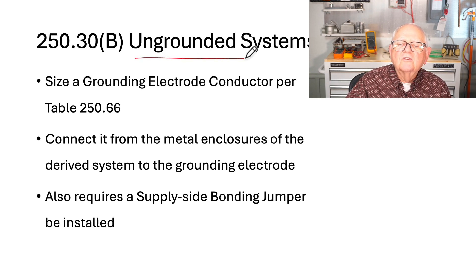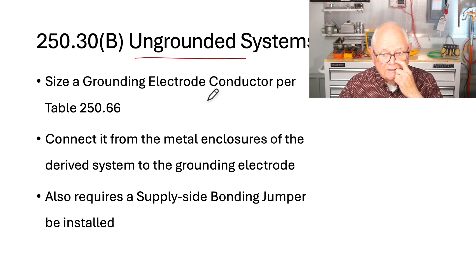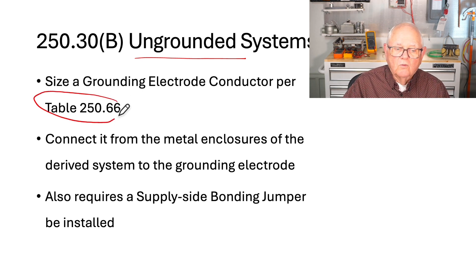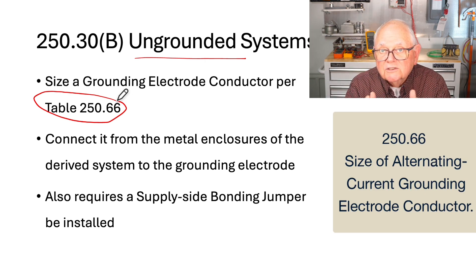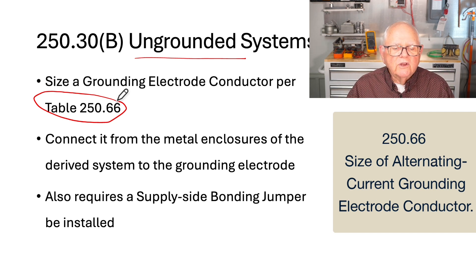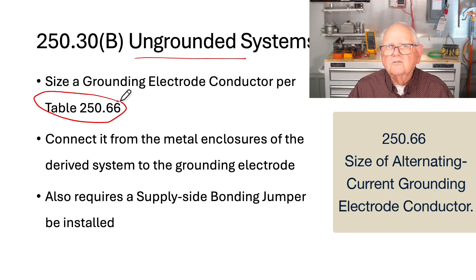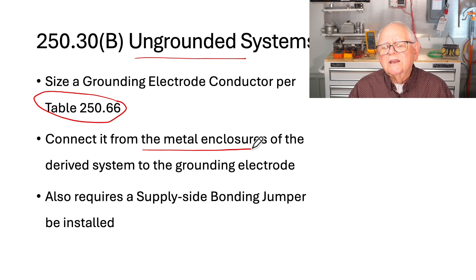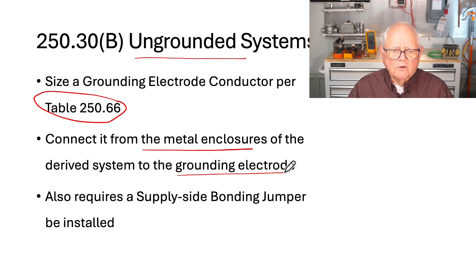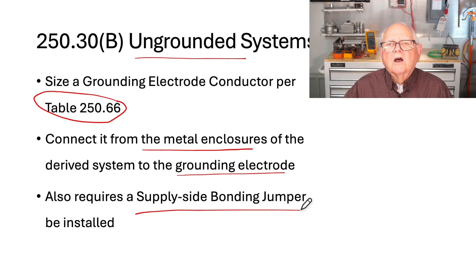What if you have an ungrounded system? You still have to have a grounding electrode conductor, sized from Table 250.66 based on the size of the derived phase conductors. However, you're not grounding your distribution system — what you're doing is connecting the metal enclosures of the separately derived system to a grounding electrode. That is the purpose of the grounding electrode conductor. It also requires a supply side bonding jumper on the supply side of the disconnecting means and overcurrent protection.